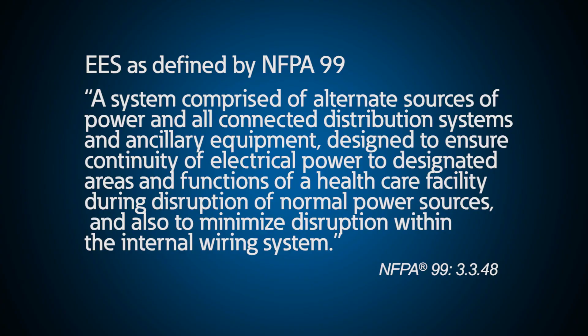NFPA defines this unique part as the Essential Electrical System, or EES. The EES is a system comprised of alternate power sources and all connected distribution systems and ancillary equipment designed to ensure continuity of electrical power to designated areas and functions of a healthcare facility during disruption of normal power sources, and also to minimize disruption within the internal wiring system.